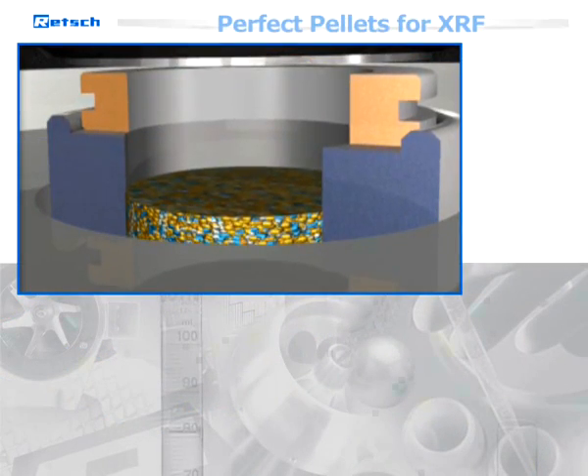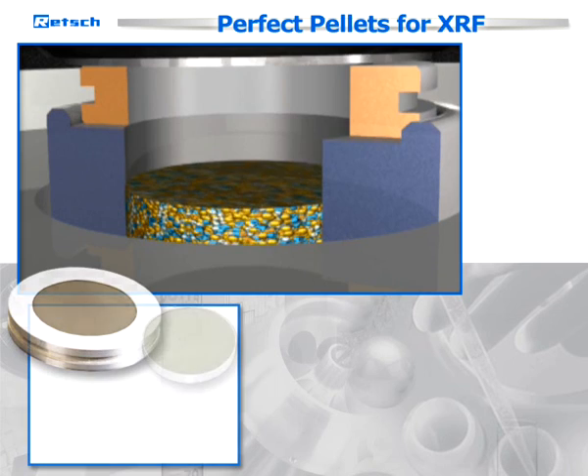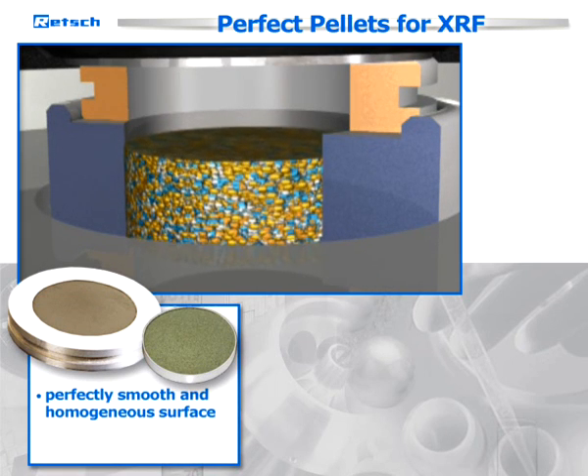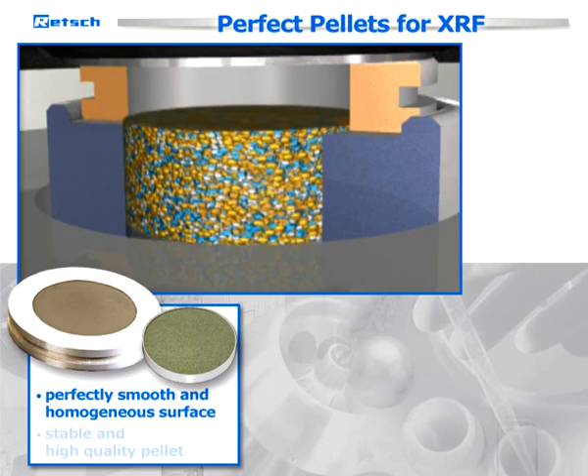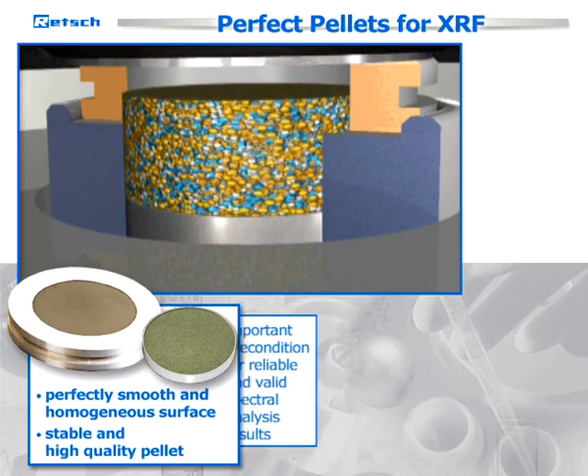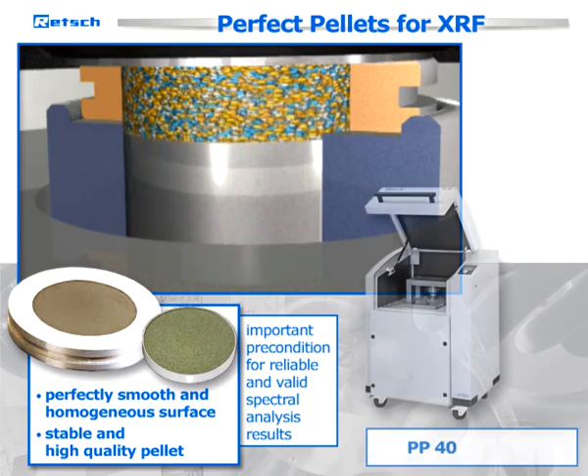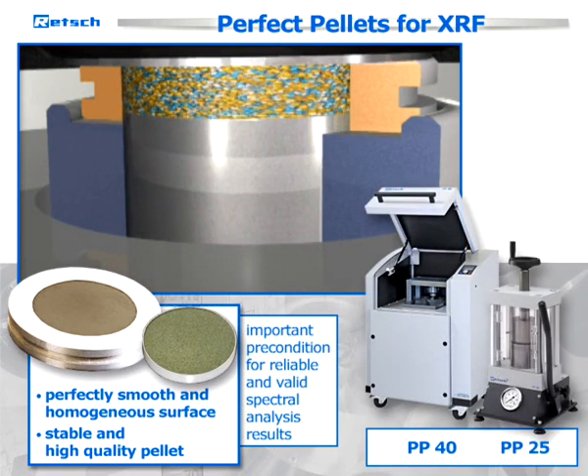After the grinding process, the material has to be pressed into a pellet with a perfectly smooth and homogenous surface. A stable and high-quality pellet is the second important precondition for reliable and valid spectral analysis results. For this purpose, Retsch offers the two pellet presses PP40 and PP25.